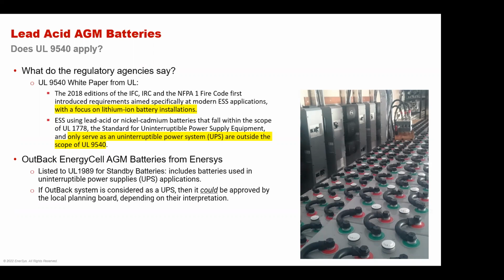People should have that, and we are going to have at some point some UL 1973 AGM batteries, but we don't as of yet. So again, the bottom line here is approval is totally up to the local authority having jurisdiction. Your AHJ is going to have the final say. The planning board that issues your permit, those are the people that are going to say whether you can still use an AGM battery or not. They may require UL 1973 or a UL 9540 DC ESS listing.